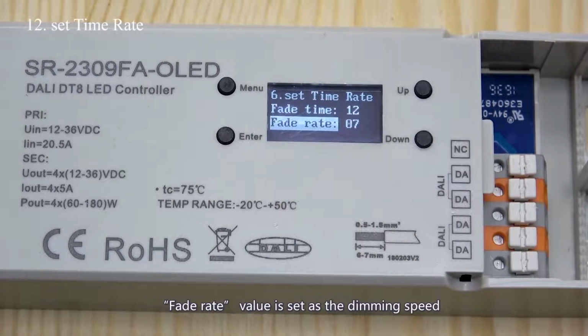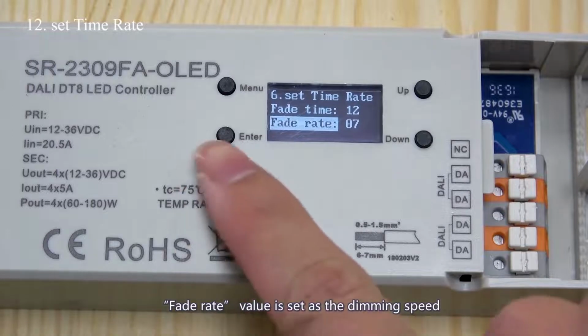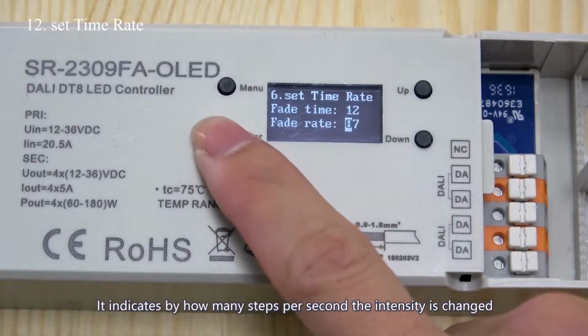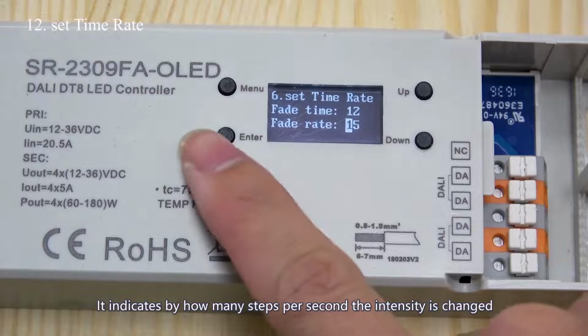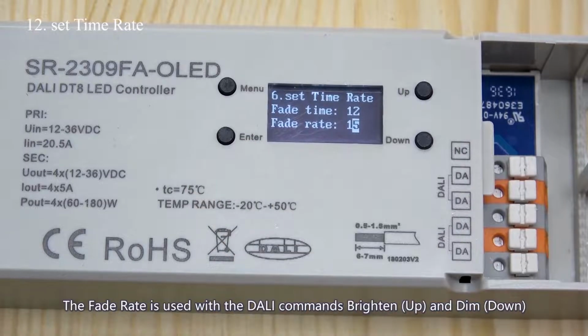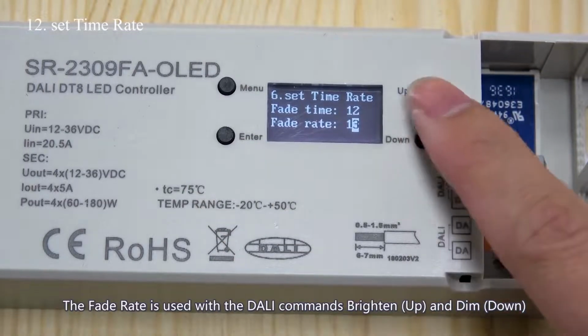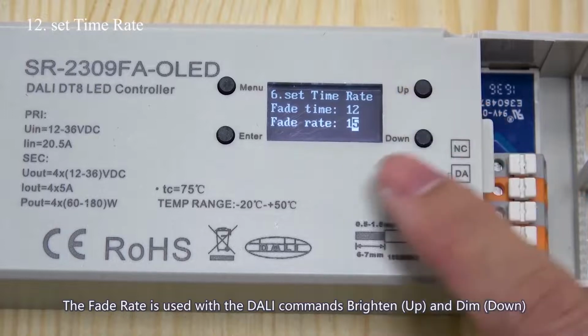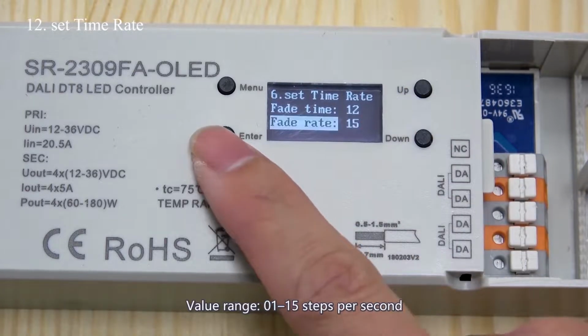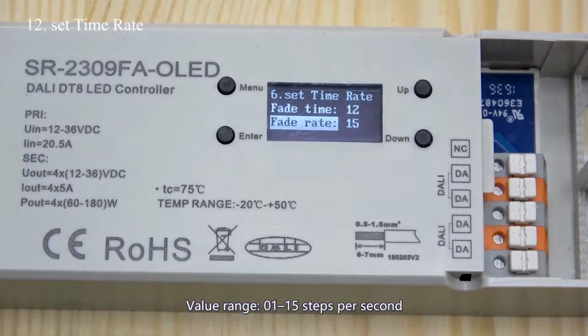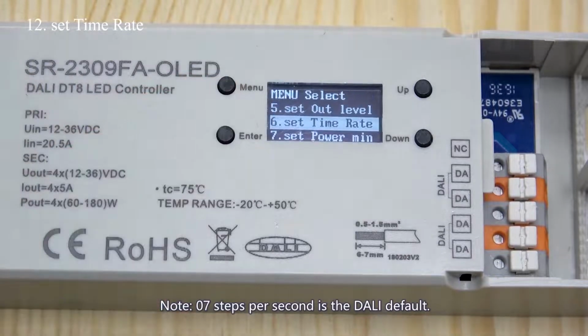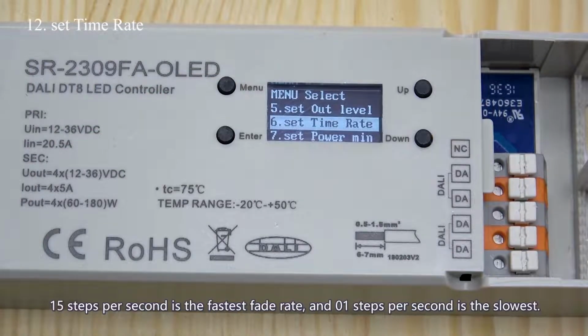Fade rate value is set as the dimming speed. It indicates by how many steps per second the intensity is changed. The fade rate is used with the DALI commands brighten up and dim down. Value range, 01 to 15 steps per second. Note, 07 steps per second is the DALI default, 15 steps per second is the fastest fade rate, and 01 steps per second is the slowest.